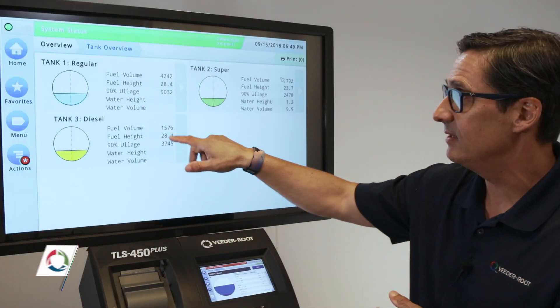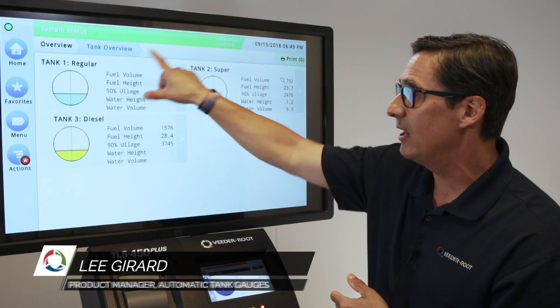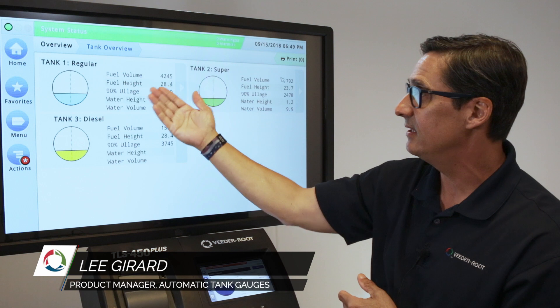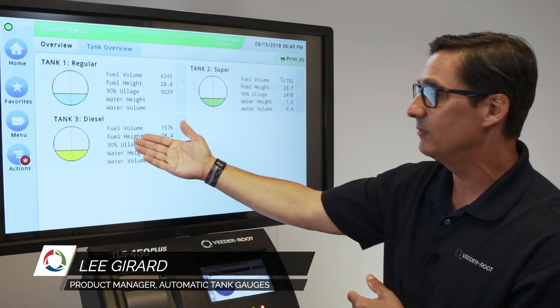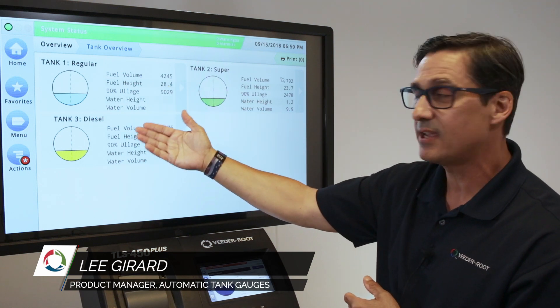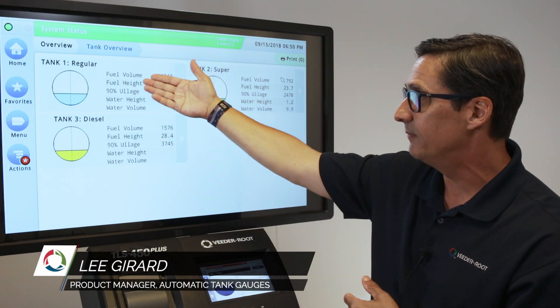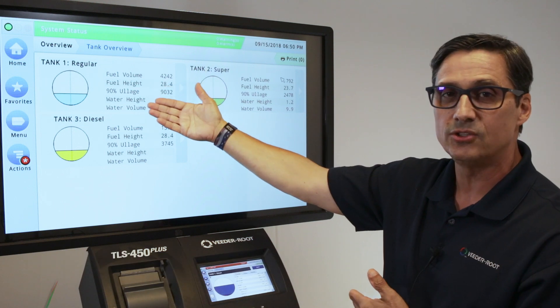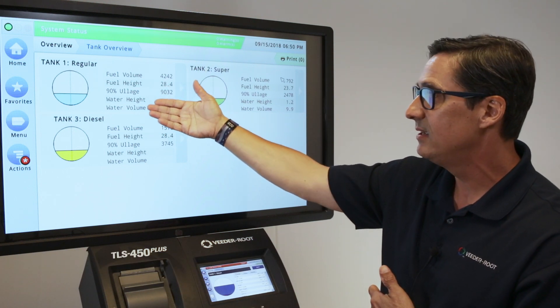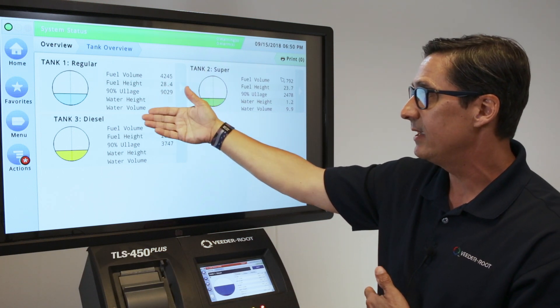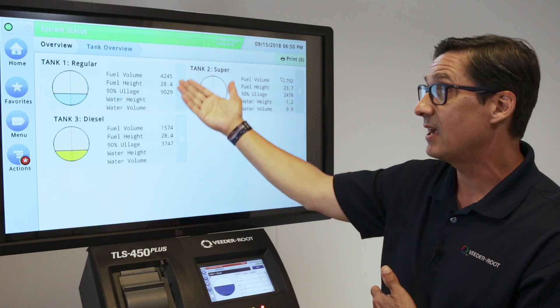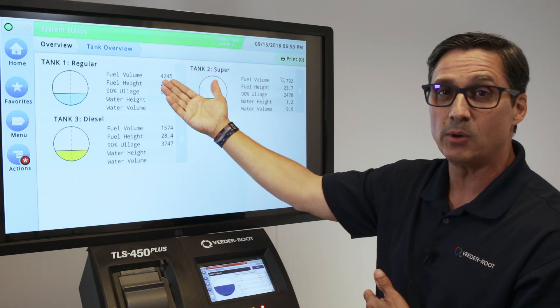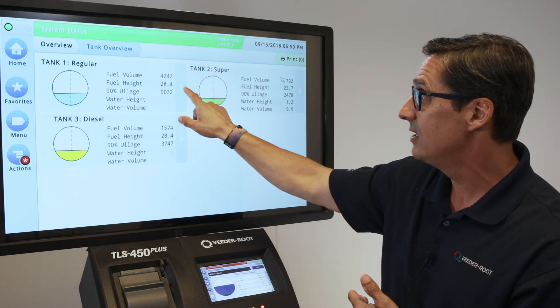What I'd like to demonstrate is how to utilize the tank overview. As you can see, it illustrates the number of tanks at the site, and more particularly it gives you the volume, the height, the ullage in the tank which is the available space, water height, and water volume. You can actually configure the console to display what you'd like based on your needs.